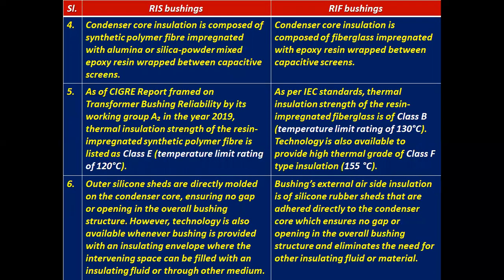Number 4, for RIS bushings, the condenser core insulation is composed of synthetic polymer fiber impregnated with alumina or silica powder mixed epoxy resin wrapped between capacitive screens. For RIF bushings, the condenser core insulation is composed of fiberglass impregnated with epoxy resin wrapped between capacitive screens.